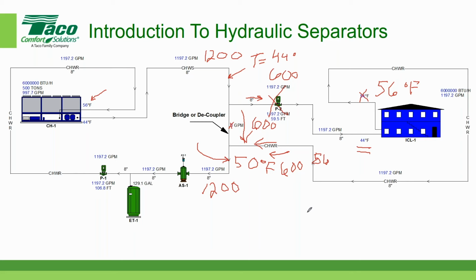Not specifically about that. There is a question about self-sensing pumps in the secondary system. So in this very simplified example, the primary flow remains constant. The primary flow is equal to 1,200 gallons per minute. So we could use a self-sensing pump in that arrangement if we chose to. The secondary flow is variable, and in this case it's going to go from roughly 20% of the design flow, so that's about 240, roughly, a minimum of 240 to a maximum of 1,200. So we could use a self-sensing pump in the secondary part, and that would be variable flow, variable speed. On the primary side, it would be constant flow, variable speed. Did that answer that question, Brett? Yep. So yes, we could use self-sensing pumps in this arrangement.